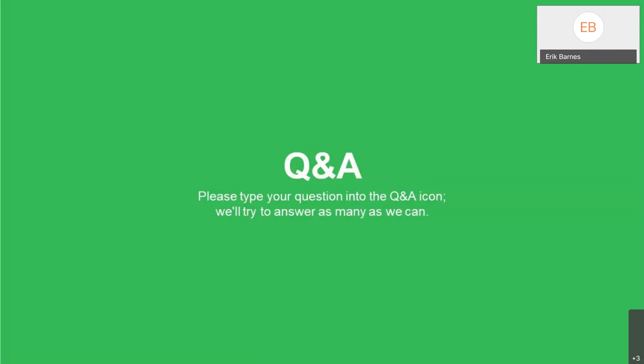Okay, thank you. We have another question here. Does the TeSys Island have a short circuit current rating? Yeah, it does. The standard default is 5 KA. If that's not an issue for you, you can go right in with the 5 KA, no issues there. But the starters have up to 85 KA with a circuit breaker at 480 volts, which is really good. They have 100 KA with fuses, either class J or class CC. We also have a 50 KA group motor option with the TeSys GV product and the starter, and that's 50 KA at 480 volts.